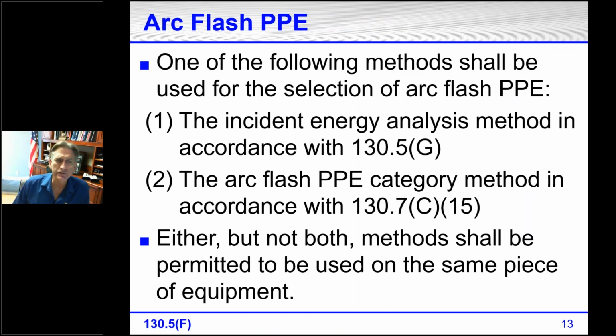One of the following methods has to be used for selecting arc flash PPE. There are two ways for knowing what PPE to use. First of all, the incident energy analysis method in accordance with 130.5G. This is where a company may come into an industrial plant and do all the calculations necessary to determine what needs to go on the label for each piece of equipment. Now, I did say it may be a company coming in. There are plenty of companies out there that have engineers on staff that do this labeling themselves, and that's fine. There's no problem with that.